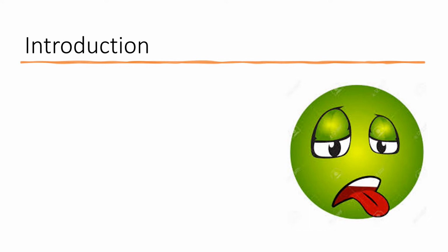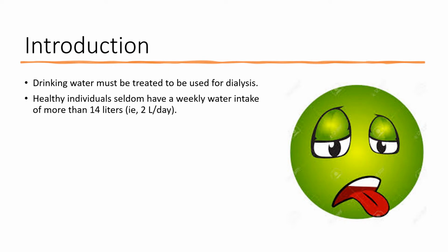As all of you know, water is used for the preparation of dialysis fluid, or dialysate, and is generally derived from either, say, a large municipal water supply or a small community water system or even from a well. Drinking water is not safe for use in hemodialysis applications and must therefore be treated further at its point of use.